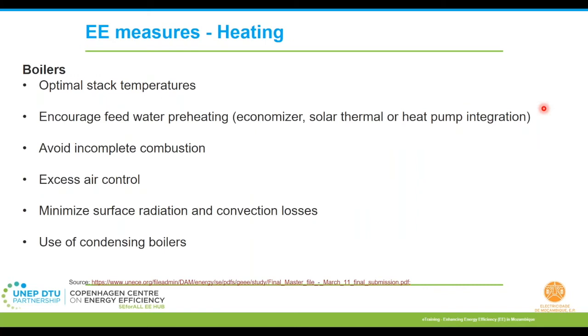For building level, boilers may not comprise a very complicated system as compared to industrial boilers. Most of the time, it is more or less a plug and play option. So in short, if you have fuel fired boilers in place, mostly applicable for hotels and large complexes where heating solutions are provided, the optimal stack temperatures need to be looked into, because these are the different forms where losses can happen. If you have higher stack temperatures, that means you are losing a lot of heat there.